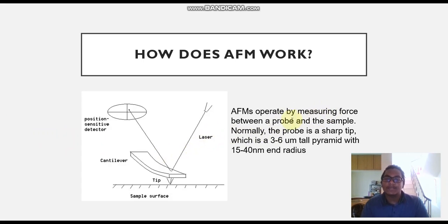The AFMs operate by measuring force between the probe and the sample, and the probe is a sharp tip with a 3 to 6 micrometer tall pyramid and 15 to 40 nanometer in radius. To put it scientifically, the working can be explained by generally measuring the vertical and lateral deflection of the cantilever by using the optical lever. The optical lever operates by reflecting a laser beam off the cantilever. The reflected laser beam strikes a photosensitive photodetector consisting of a 4-segment photodetector. To put it simply, the laser beam strikes a ray of light and it reflects back to the photosensitive detector.